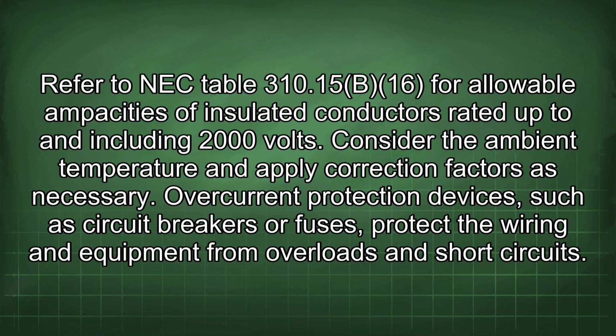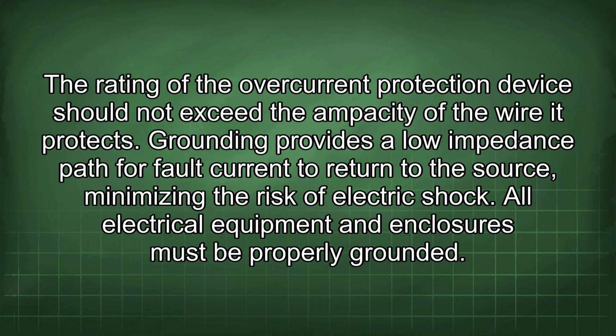Refer to NEC Table 310.15(B)(16) for allowable ampacities of insulated conductors rated up to and including 2000 volts. Consider the ambient temperature and apply correction factors as necessary. Overcurrent protection devices, such as circuit breakers or fuses, protect the wiring and equipment from overloads and short circuits. The rating of the overcurrent protection device should not exceed the ampacity of the wire it protects.